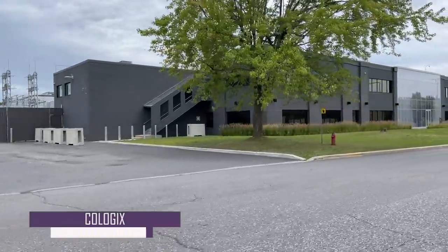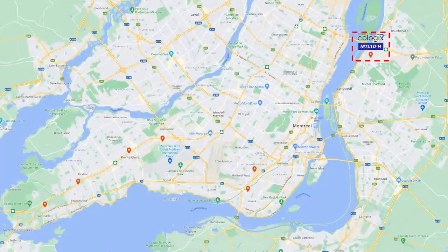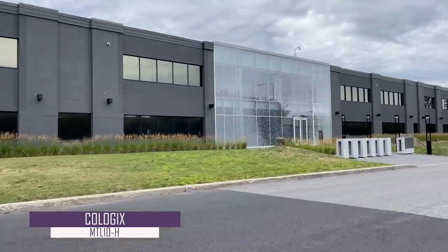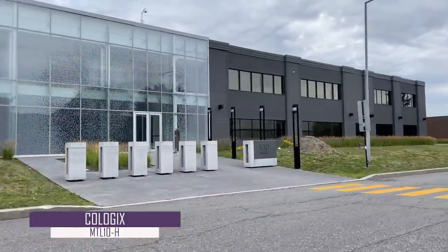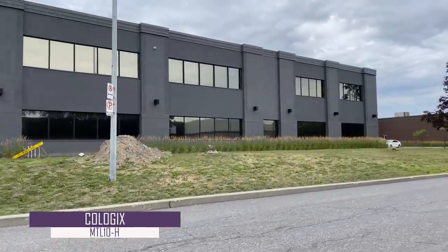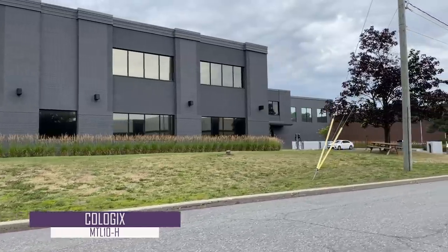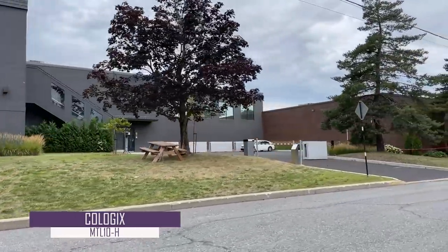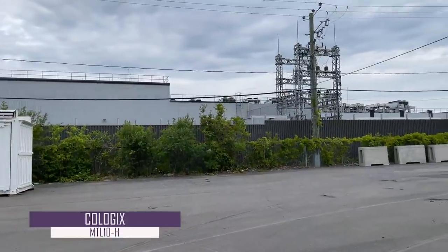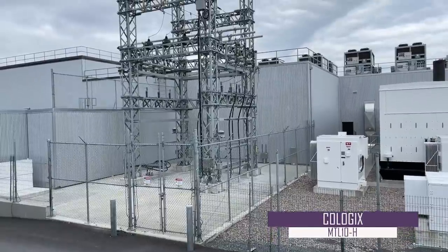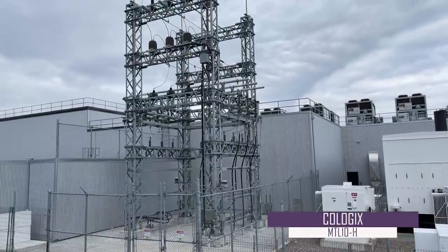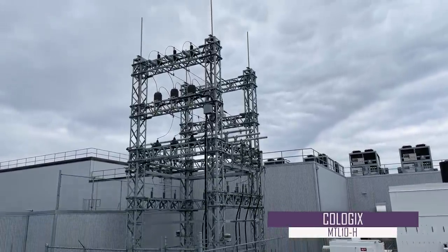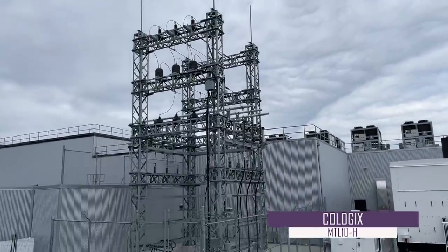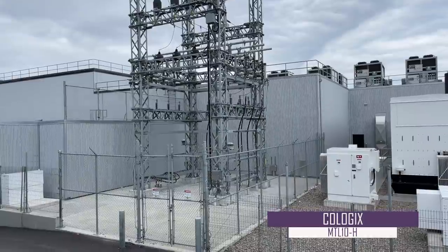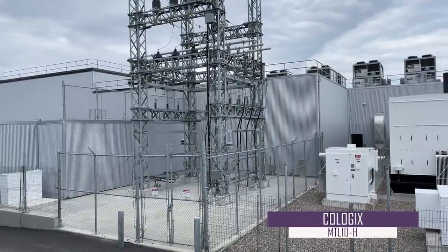Cologix's MTL-10 is a hyperscale data center in a suburb of Montreal on the south shore of the St. Lawrence River. The facility can provide 35 megawatts of critical power across 180,000 square feet. Additionally, the company has plans to expand the facility to 50 megawatts of power and 240,000 square feet. As you can see, Cologix has a substation on site, which supplies the data center with 100% renewable power from utility company Hydro-Québec. This power is then channeled into 9 megawatts of power for each data hall within the facility, with up to 30 kilowatts per server cabinet.